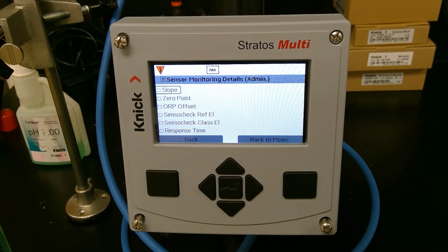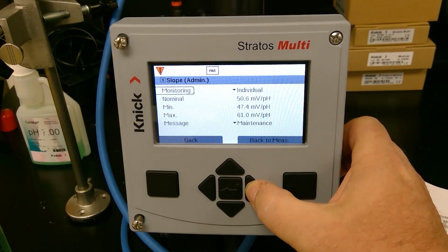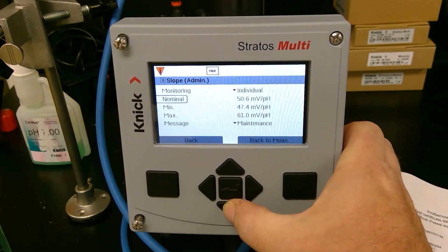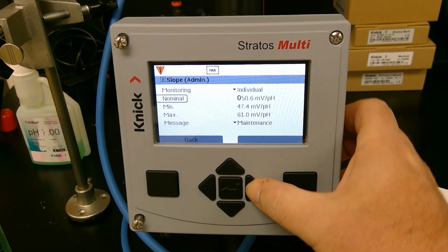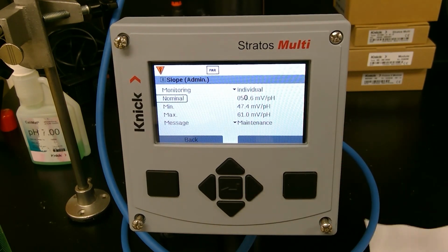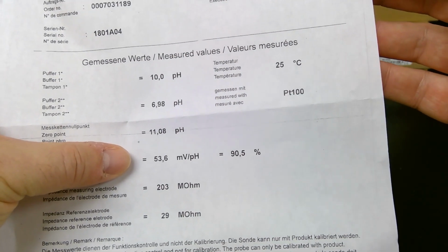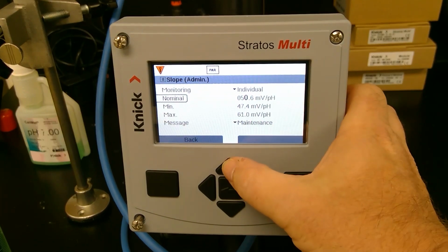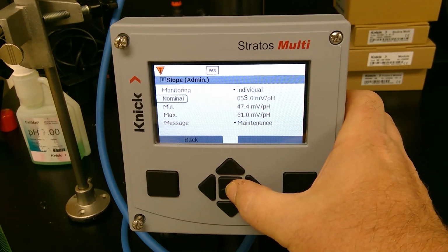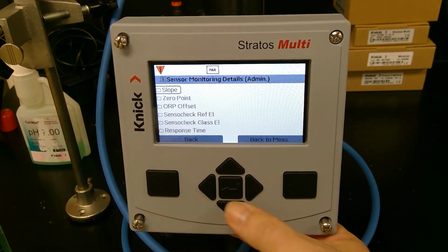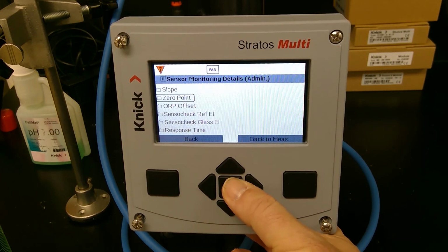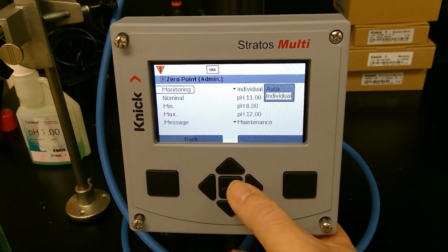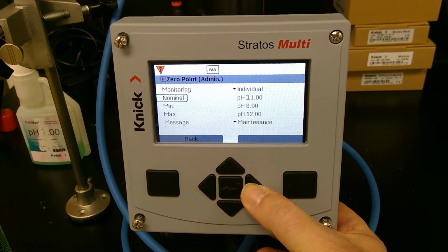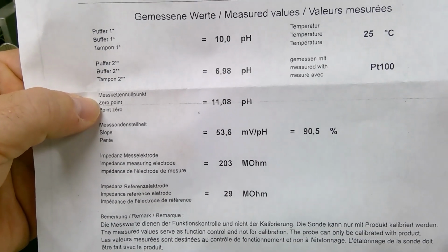So let's start with the slope. I hit enter. Make sure it's set to individual. And we're only going to adjust the nominal slope. Now, on this particular probe, the nominal slope is 53.6. All right, that is what we need to put into right there. So I hit enter. Next, I'm going to adjust the 0 point. Again, make sure it's set to individual. The 0 point for this Type 18 is 11.08.